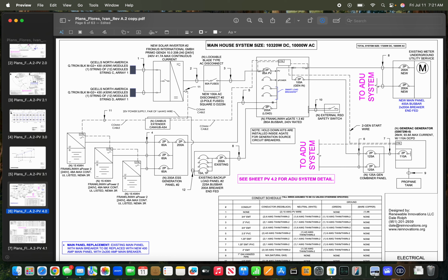So this is the main house, getting the biggest part of the design. As you can see, we have 10.32 kilowatts of DC energy, that's 10,320 watts, and a 10,000 watt AC inverter, so we're pretty close to a 1-to-1 ratio. It's okay if your DC rating is greater than your AC output; that tends to be pretty standard, especially with microinverters. Keep that in mind.